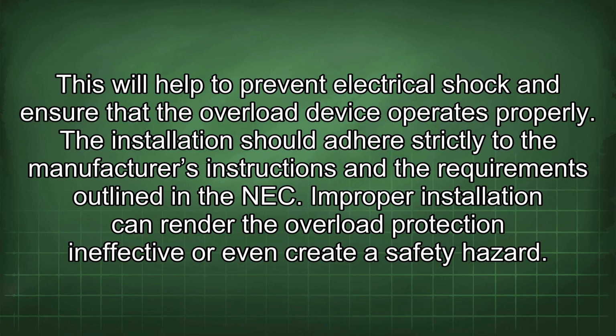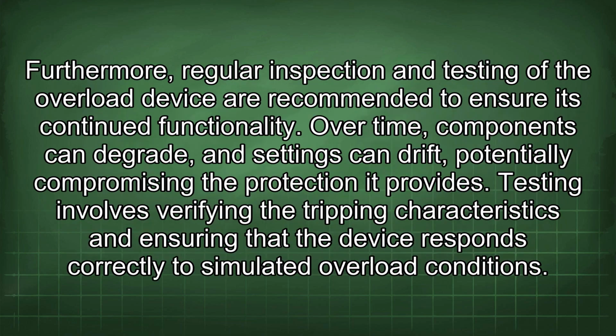The installation should adhere strictly to the manufacturer's instructions and the requirements outlined in the NEC. Improper installation can render the overload protection ineffective or even create a safety hazard. Furthermore, regular inspection and testing of the overload device are recommended to ensure its continued functionality. Over time, components can degrade and settings can drift, potentially compromising the protection it provides. Testing involves verifying the tripping characteristics and ensuring that the device responds correctly to simulated overload conditions.